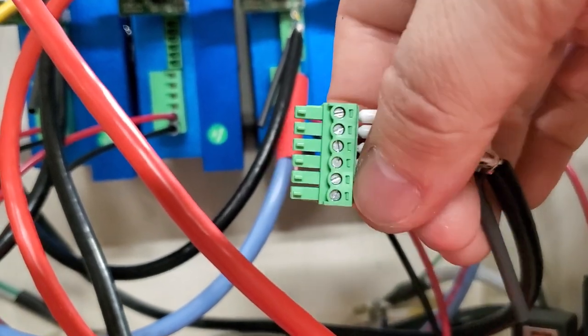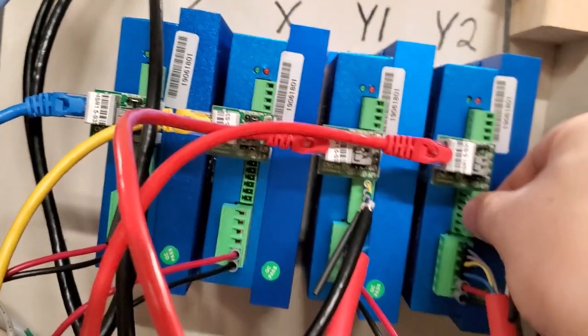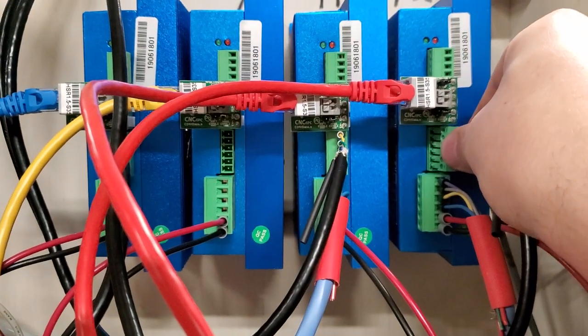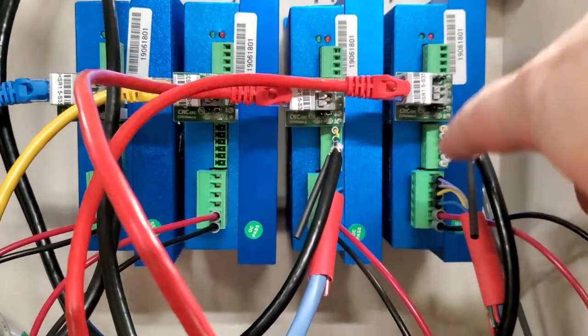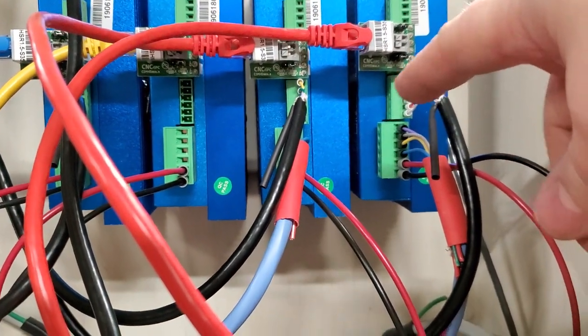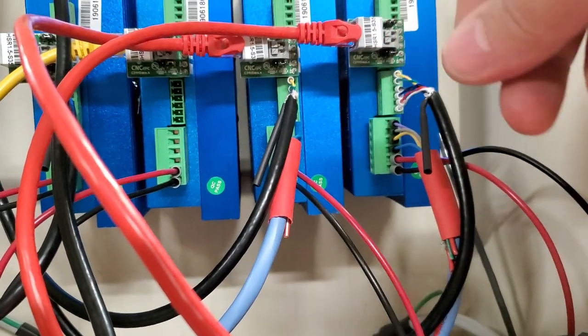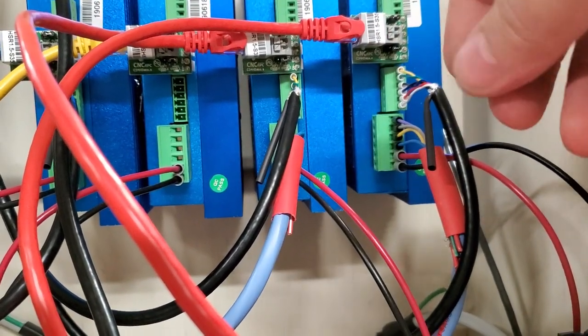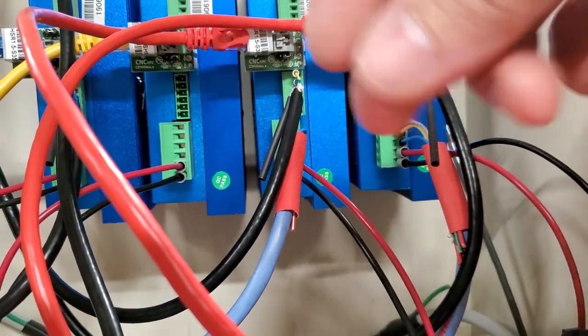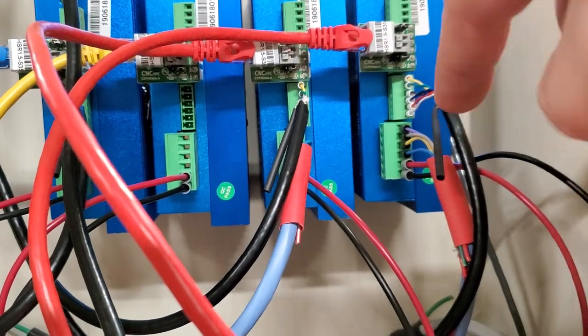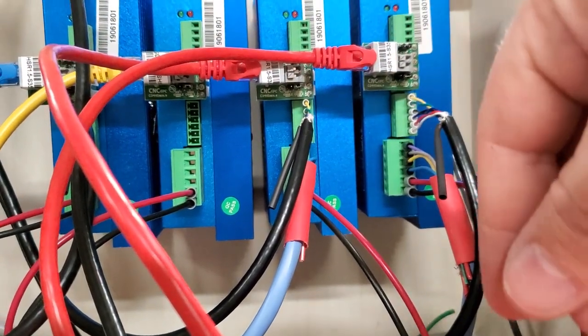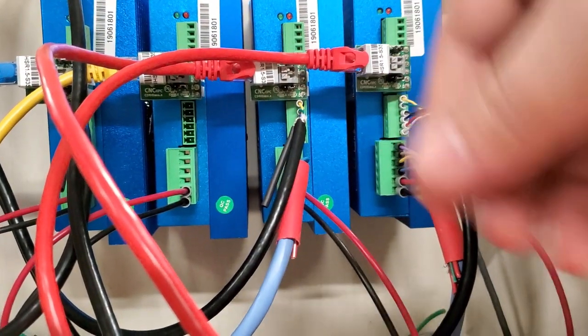They're all nicely insulated from one another. And the best part is, if you're troubleshooting you can pull them out of the little terminal block and you can test them and then you can put them back in. And you don't have to worry about twisting the wires back up when you stick them in and possibly causing a short or some other tech-created error.